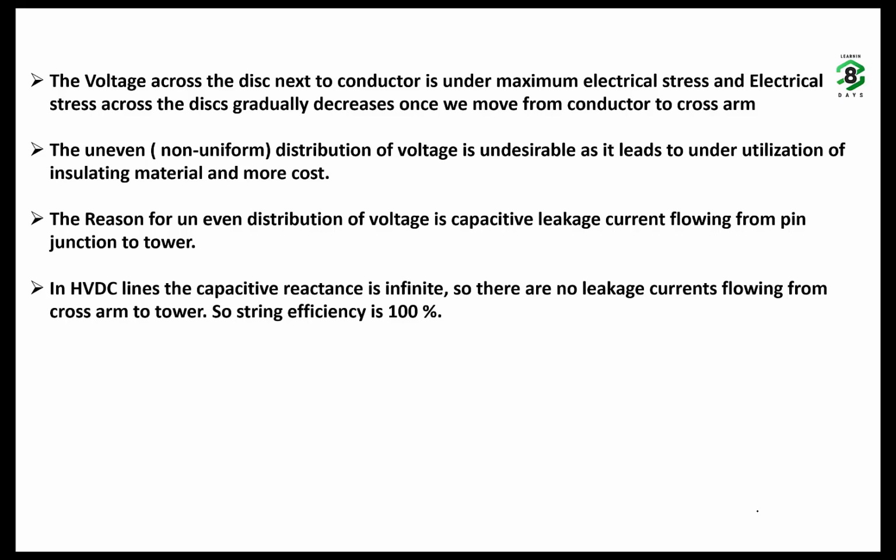The voltage across the disc next to the conductor has maximum voltage and maximum electrical stress, but as we gradually move from conductor to the cross arm, the voltage decreases and electrical stress also decreases.